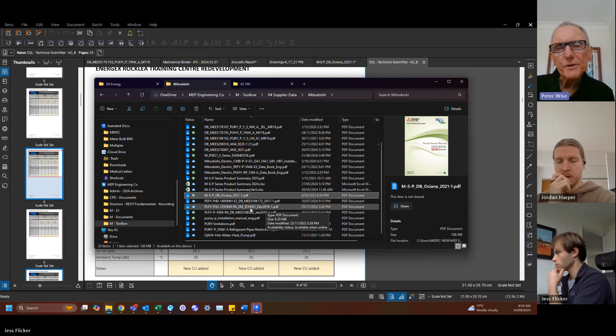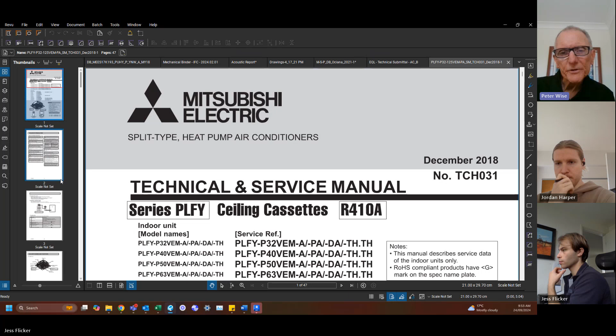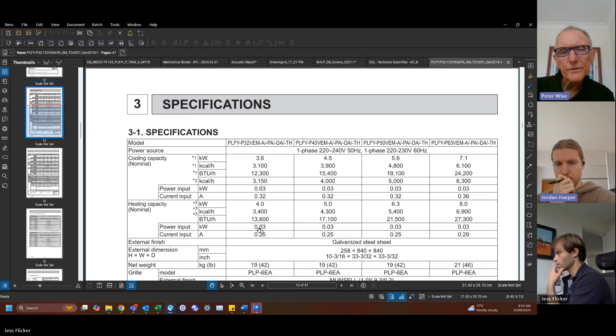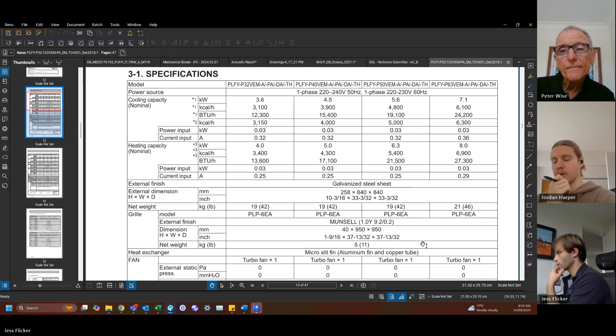Even though it could potentially get loud if they put it higher, you've specified that it only needs to be on the lowest setting. That needs to be documented in some way so you're covered. If they come back and say it's too noisy, as long as you've told them you selected it for that speed, and if they choose to turn it to a higher speed it may exceed the specified sound level, then you're okay.